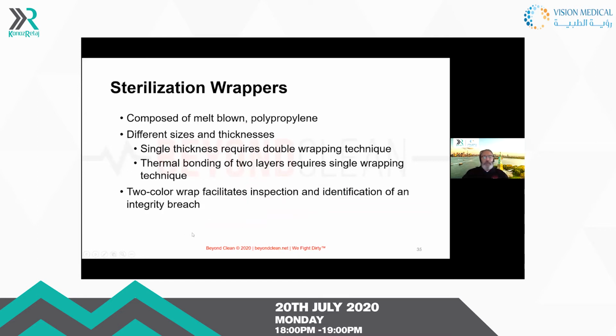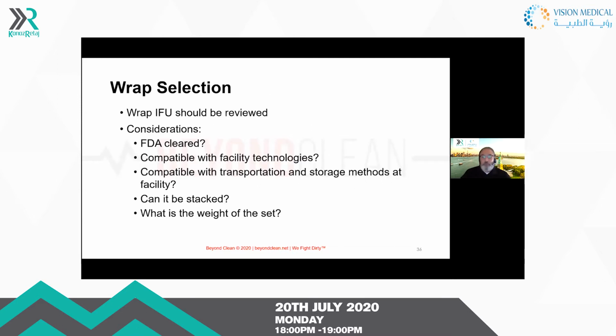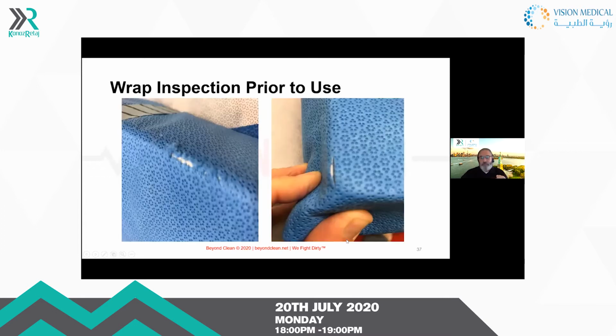So we know that wrappers are composed of polypropylene. It's a melt process. They are single thickness, often thermal bonded with 2 layers. They have some new ones that have different colors. We want to make sure that they're always FDA cleared. They're compatible with our technologies. We want to, again, make sure that they can, in fact, be stacked before we stack them. And what is the appropriate weight of the sets? We know it's 25 pounds.